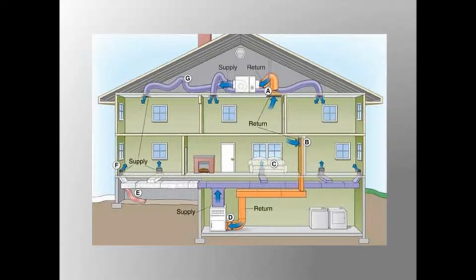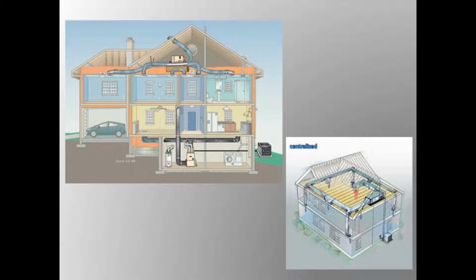HVAC systems integrate both heating and cooling into one system. HVAC systems use air, water, or both to distribute heating and cooling energy. Most systems use furnaces, which supply hot air, and boilers that heat water or produce steam. System selections are made by a mechanical engineer based on performance, efficiency, and initial life costs of the system. HVAC equipment can take up between 10 and 15% of the building area. Depending on climate, heating and cooling needs and concerns will be addressed with the selection of either centralized or localized equipment by the mechanical engineer.